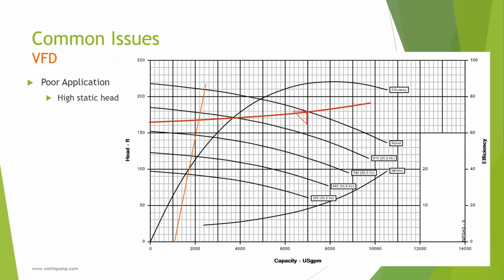One of the worst applications is a high static system head because the curves are relatively flat. This example shows a pump that can only reduce its speed by about 10% before it's outside the allowed operating range. So this has a 10% operating range, which is probably not the energy savings an owner is expecting. We recommend using a VFD on systems with high friction losses. It allows the pump to reduce speed and stay within the allowed operating range for a much higher turndown rate.